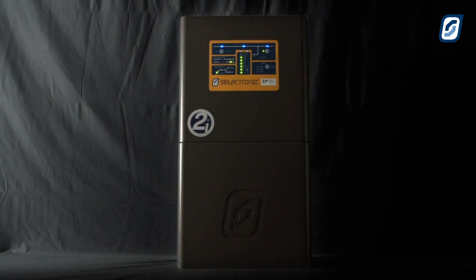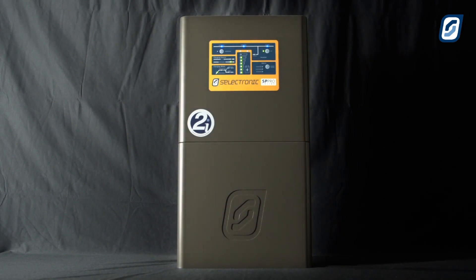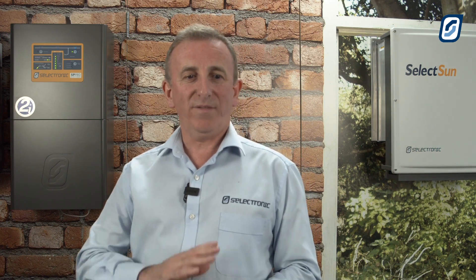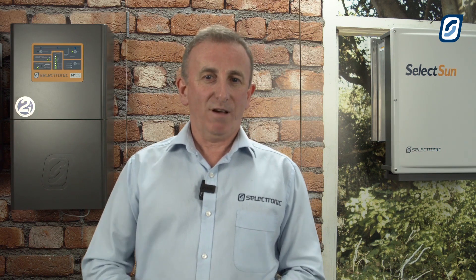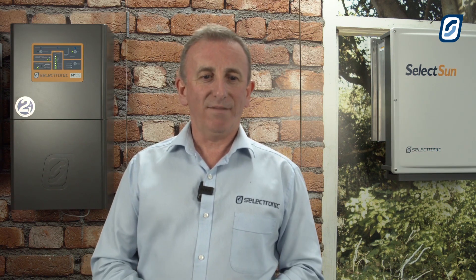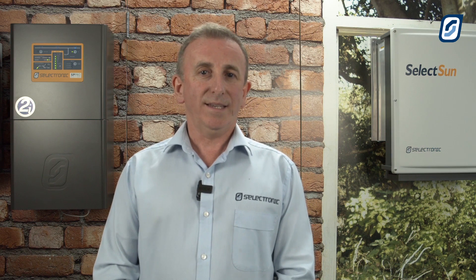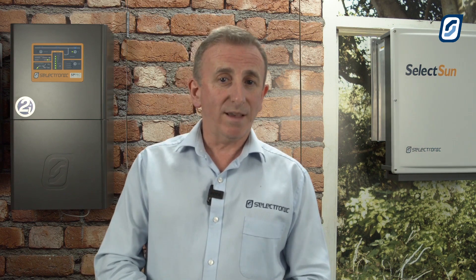It's a true 3-phase output. The SPMC480 comes in the all-new 2i series configuration, meaning all the communications you need for managed batteries, dual phase or 3-phase are all standard — minimizing time on site for the installers. AC coupling recovery mode is also standard in this model, which allows a black start in an AC-coupled solar system. More on that in another video, or you can turn to page 70 of our SP Link manual.